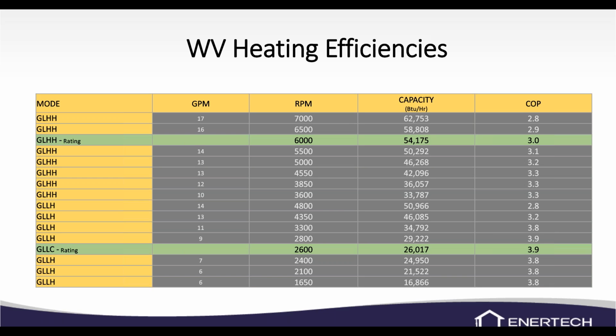And then when we're running up at that higher RPM range, normally I don't see the units go much above about 6,500 RPMs. At 6,000 RPMs, you're going to be at about a 3.0 COP. So if you need to know these efficiencies a little bit more, it is in our IOM.